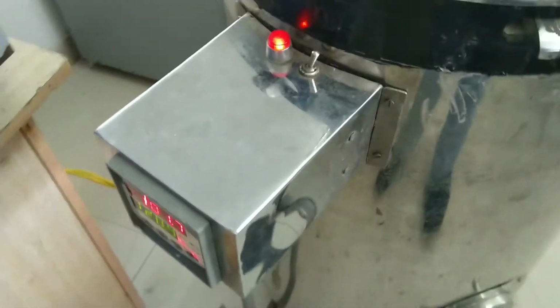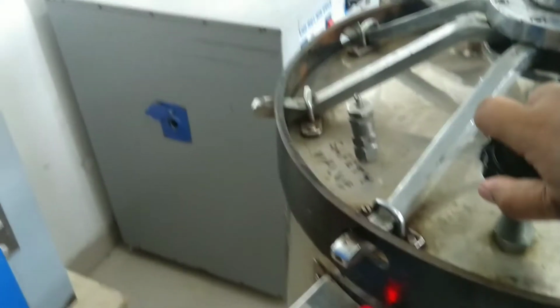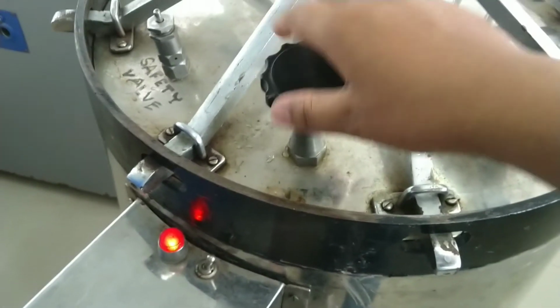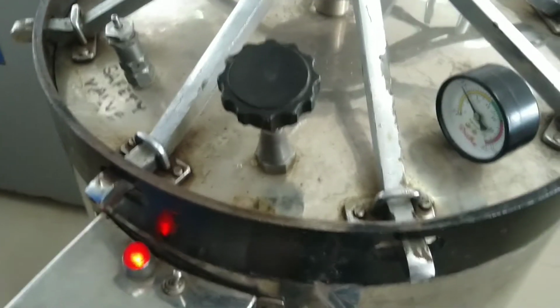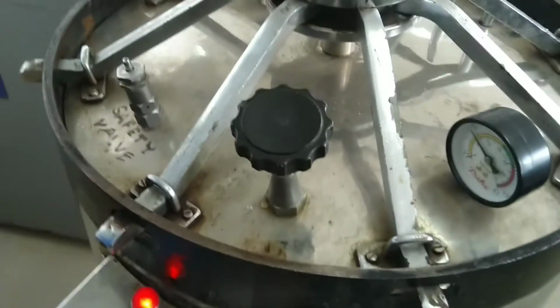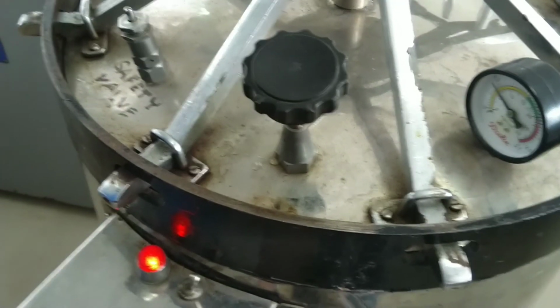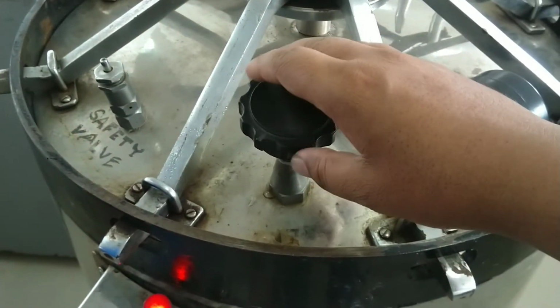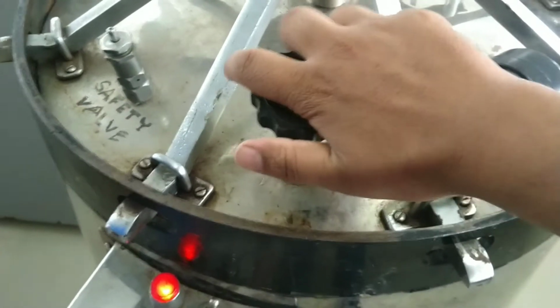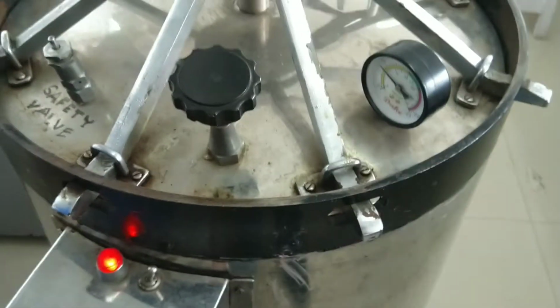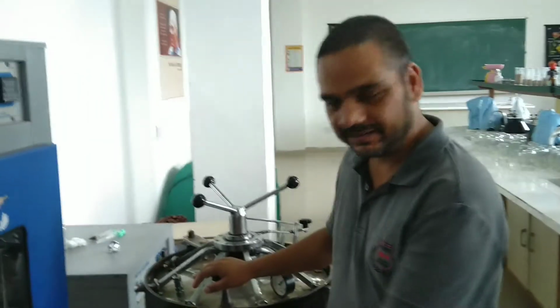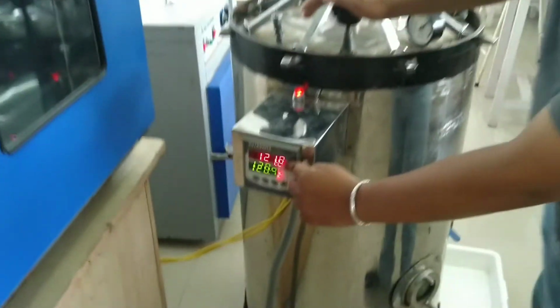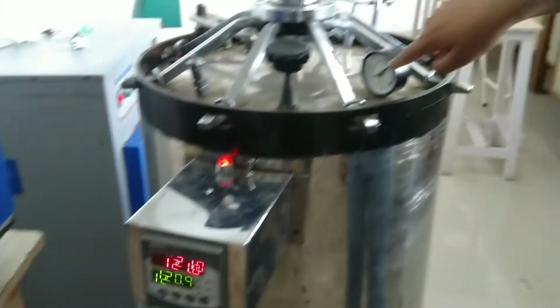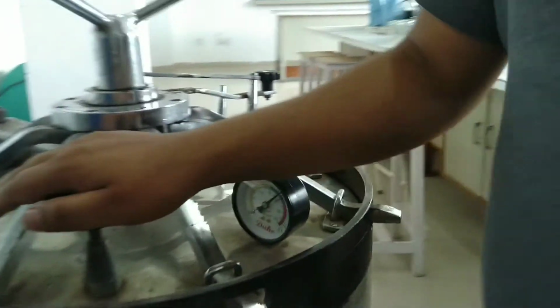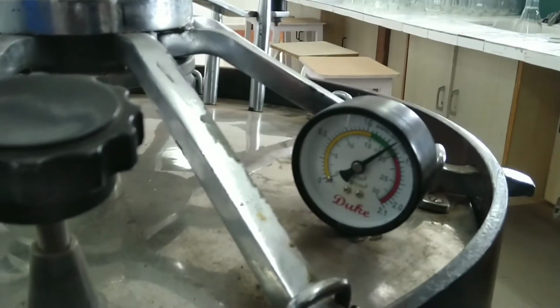Now when the temperature reaches 100 degrees Celsius, you will release some of the steam so that no vacuum will be formed and heat will be distributed evenly throughout the autoclave. After releasing steam, you will close the pressure valve properly and wait until the temperature reaches 121 degrees Celsius. Now the temperature has reached 121 degrees Celsius and the pressure has reached 15 lbs psi. Now we will wait for 15 minutes.